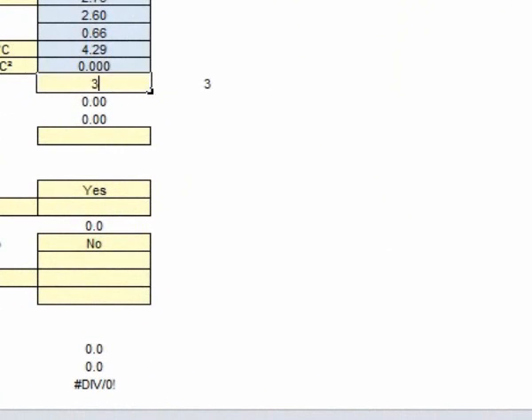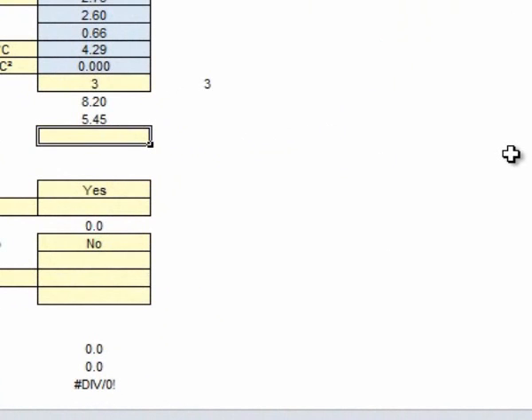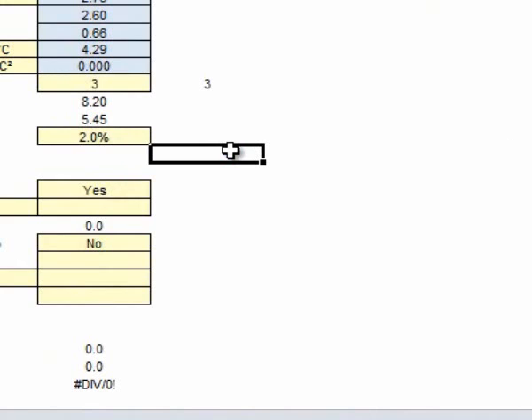So I'm going to select 3. Now, miscellaneous losses. There are quite a few videos out there already and I'll have links to those as well. But miscellaneous losses, those guys are saying that it's 2% per collector. So in this case it would be 6%.